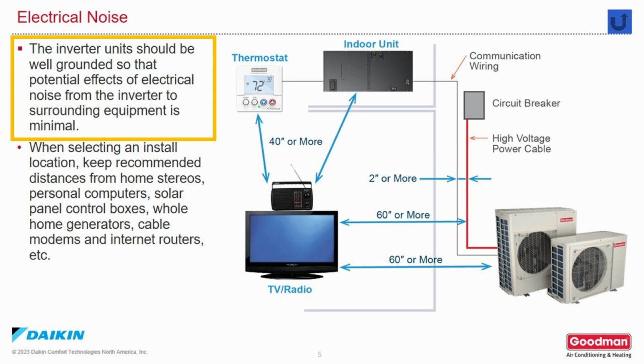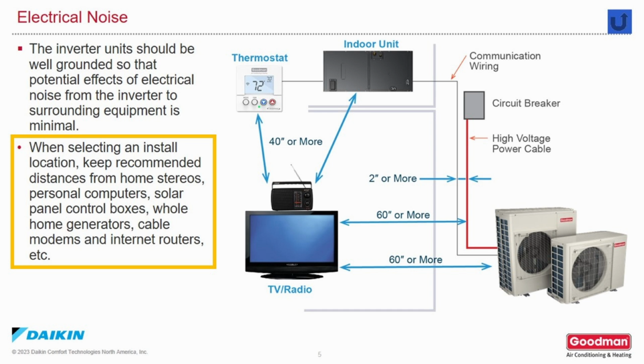Since inverter-driven equipment utilizes digital communications between its components, it is important to keep the communication circuit a safe distance from devices that can create electromagnetic fields or radio frequency, such as televisions, radios, stereo systems, solar control panels, whole house generators, cable modems, internet routers, that sort of thing. RF or EMF interference can cause erroneous operation of the system.